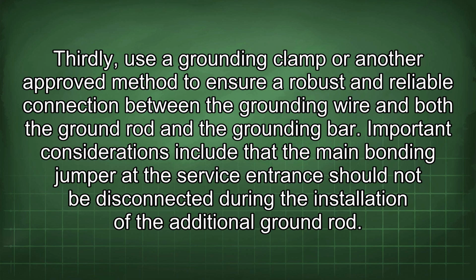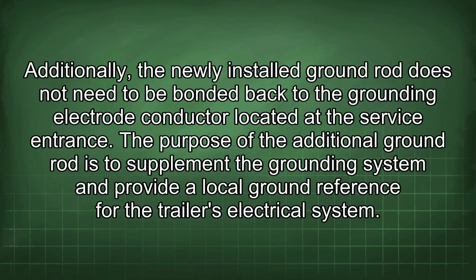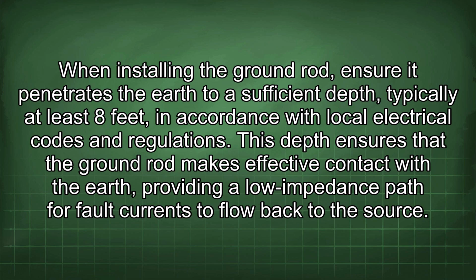Important considerations include that the main bonding jumper at the service entrance should not be disconnected during the installation of the additional ground rod. Additionally, the newly installed ground rod does not need to be bonded back to the grounding electrode conductor located at the service entrance. The purpose of the additional ground rod is to supplement the grounding system and provide a local ground reference for the trailer's electrical system. When installing the ground rod, ensure it penetrates the earth to a sufficient depth, typically at least 8 feet, in accordance with local electrical codes and regulations.